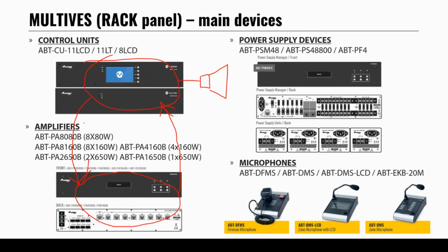Why do we need that loop here, where we first go over and then back from the main amplifier to the control unit? It is for surveillance, because the control unit is monitoring here - there is always a measurement of the output of the amplifiers, so the control unit can detect if an amplifier is failing and there is no sound. It can then use another amplifier, a spare backup amplifier, to deliver sound to the speakers in case one of the amplifiers is gone, because failures can happen.